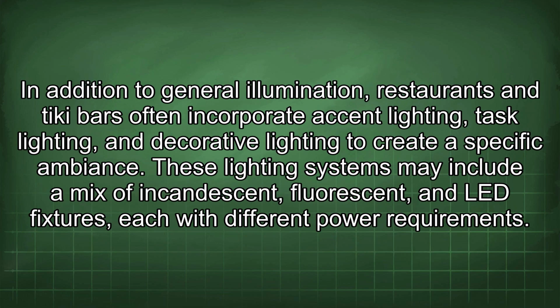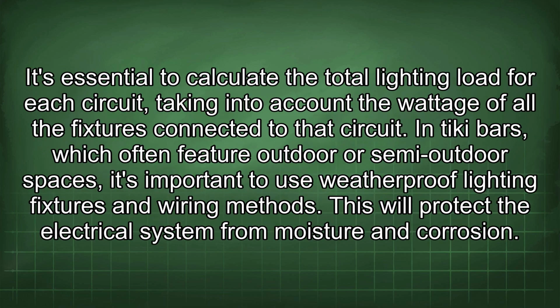In addition to general illumination, restaurants and tiki bars often incorporate accent lighting, task lighting, and decorative lighting to create a specific ambience. These lighting systems may include a mix of incandescent, fluorescent, and LED fixtures, each with different power requirements. It's essential to calculate the total lighting load for each circuit, taking into account the wattage of all the fixtures connected to that circuit.